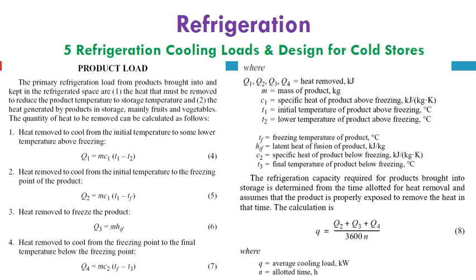Then we will switch to the second load component, which is the product load. The primary refrigeration loads from products brought into and kept in the refrigerated space are: 1. The heat that must be removed to reduce the product temperature to the storage temperature. And 2. The heat generated by the products in storage, mainly fruits and vegetables. The quantity of heat to be removed can be calculated as follows.